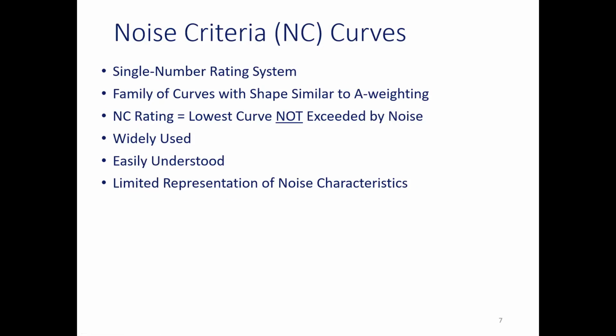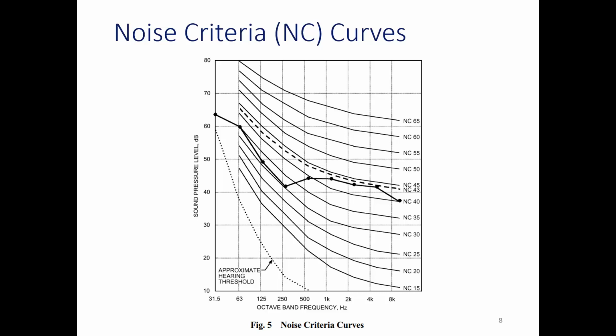Now we're going to talk about some criteria. First, we have noise criteria curves, or NC curves. This is just a single number rating system. This will make more sense on the next slide, but it's a family of curves with shapes similar to A weighting, so let's go and look at it. We'll come back and forth. All of these are a family of curves similar to A weighting, right? We're less sensitive to low frequency sound and more sensitive to higher frequency sound, so they follow that same shape. They're numbered 15, 20, 25, 30, 35, 40, and so on.